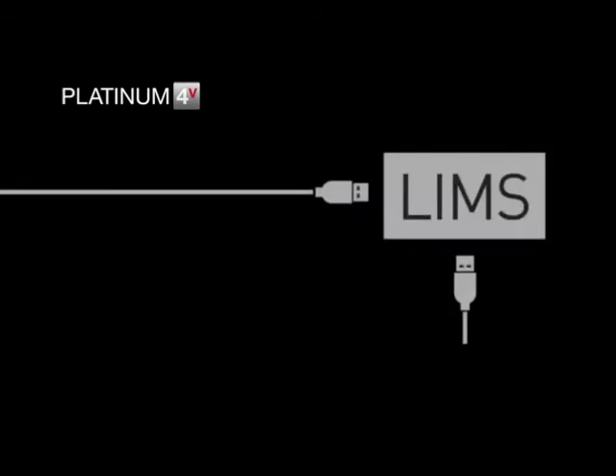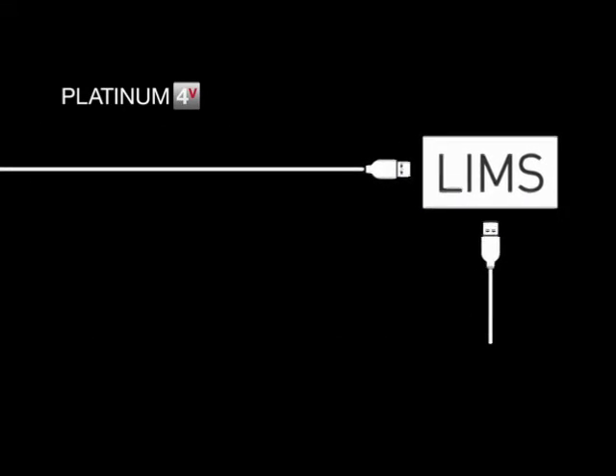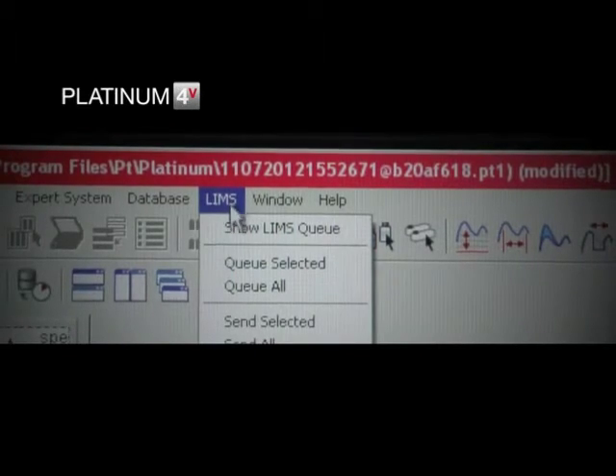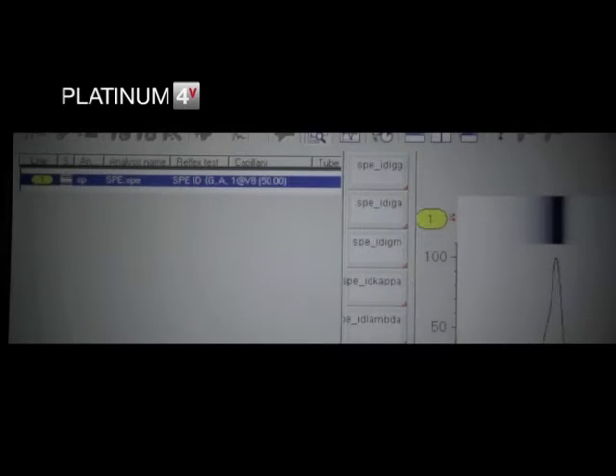LIMS integration and the advanced capabilities of Platinum 4V have culminated in the creation of the Expert System, which intelligently identifies and orders retests of abnormal samples. This is configured by the users to give the flexibility they require.